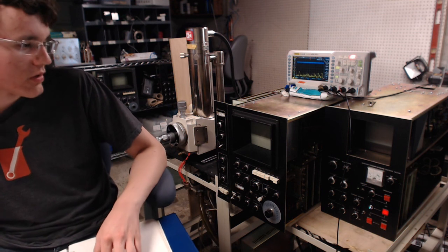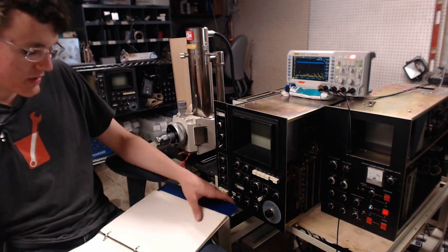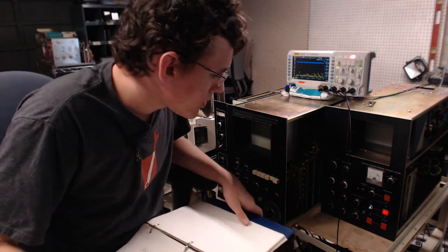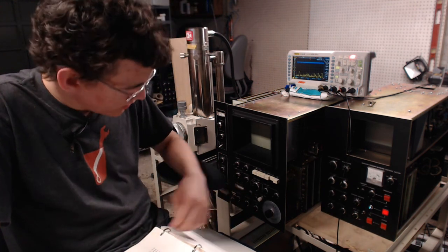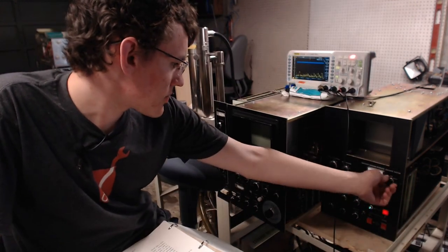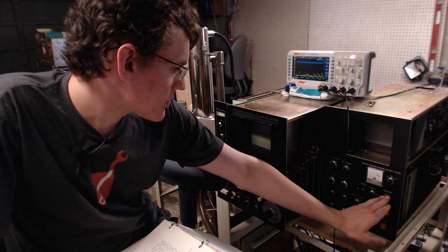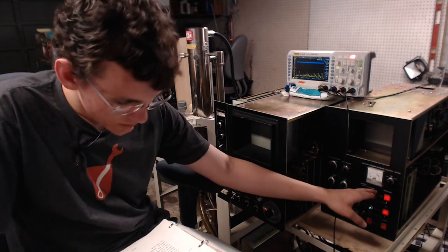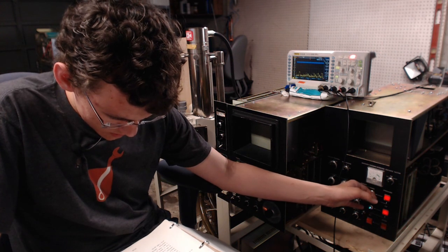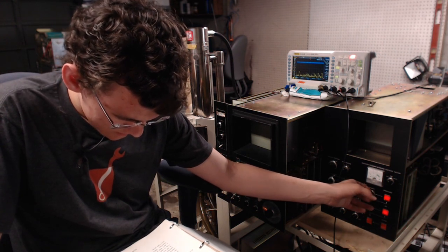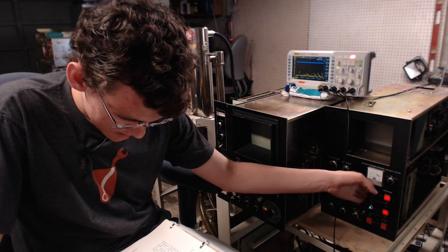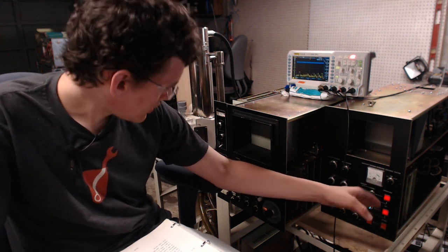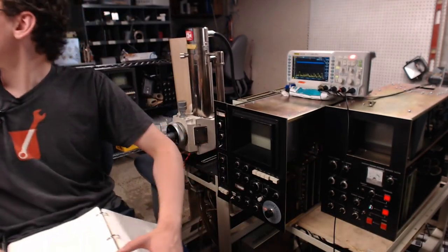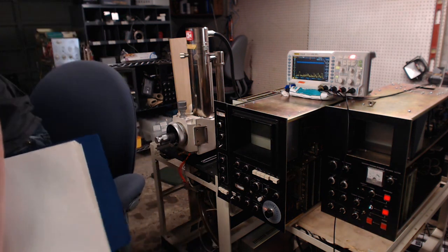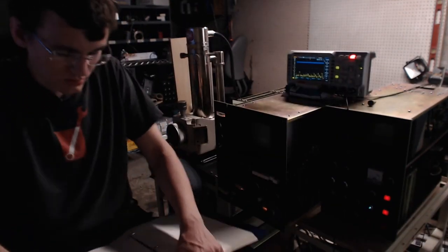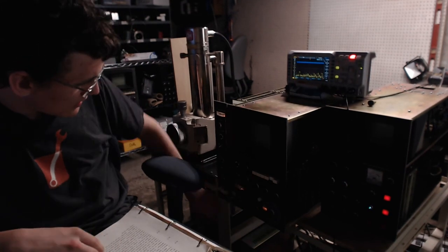So, reading the manual, it could be a bit of contamination, and it gives me an easy test to do. So, let's see here. Vacuum's good. With instrument enabled. Leave that in counterclockwise. Turn light on. Adjust brightness to comfortable level.